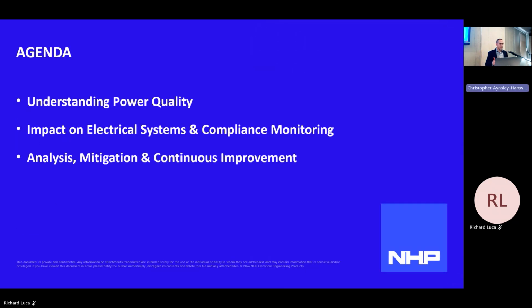So the agenda is split up into three sections. We've got first section, which is understanding power quality. So that's looking at harmonic behaviour pretty closely. Then the impact of electrical systems, compliance monitoring. So looking at some loads, affected loads and issues caused, and some compliance requirements there according to standards. And then the analysis, mitigation and continuous improvement. So utilising a site-wide monitoring system.